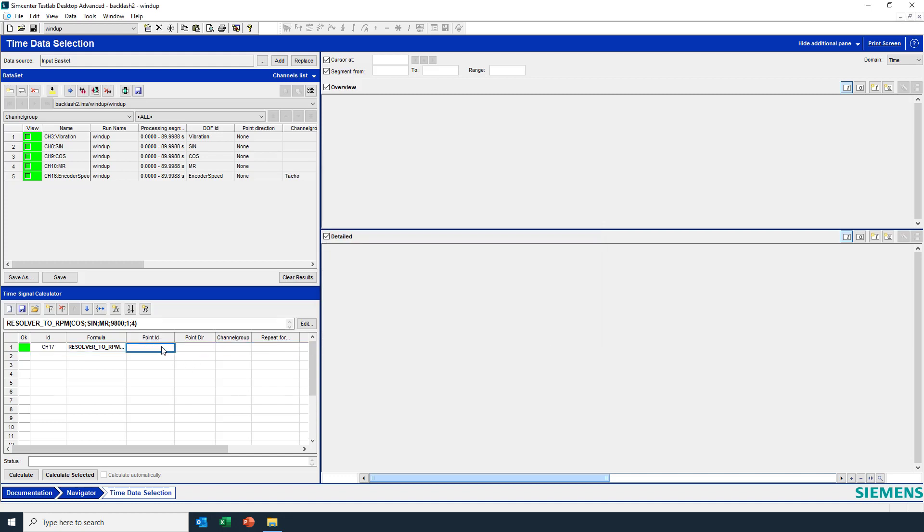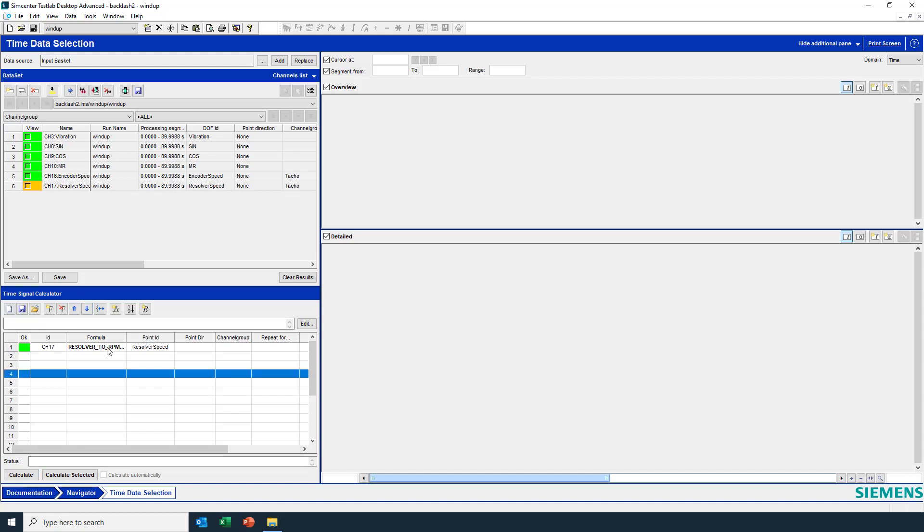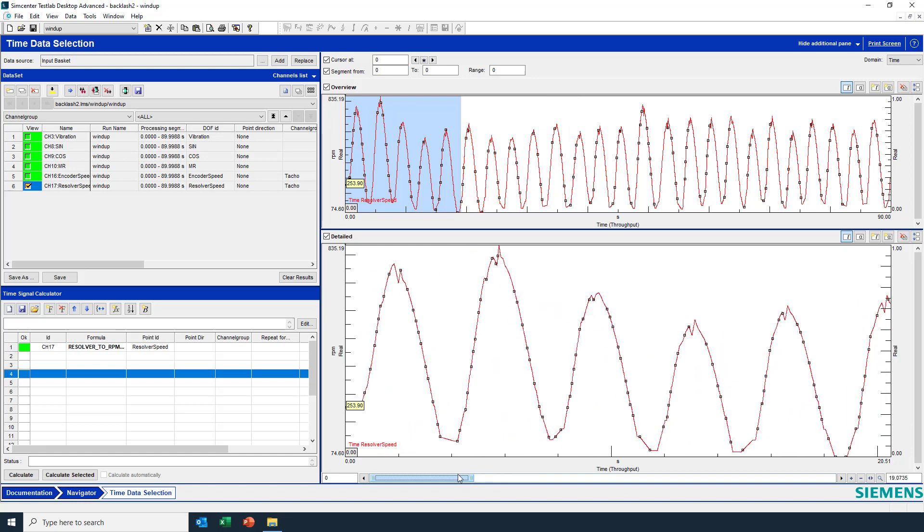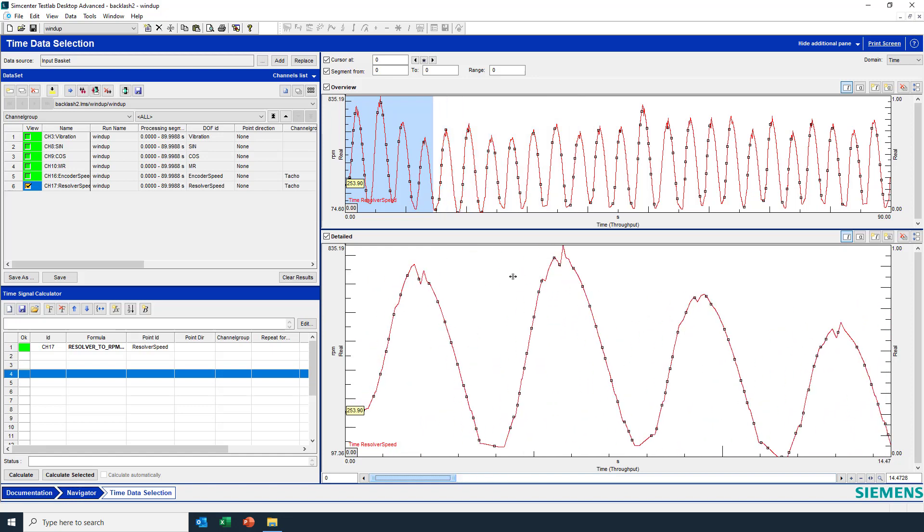This ID I can call the resolver speed. Now I'm interested in the angular position, but by calculating the resolver speed I can first verify because I know the rpm should be between 70 and 840 rpm or so. I can verify that the rpm is correct, and now I know that I've entered the resolver parameters correctly.